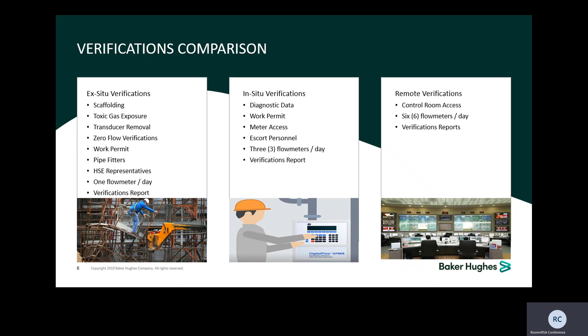We're able to do digital verifications thanks to the Flare.IQ software. It pulls information out, and I have a schematic that talks about this. All this information is sent back to the DCS connected to our Flare.IQ box, and from there we get all the data and analysis to determine pass or no pass. Because our guys go out to the DCS control room, we don't have to access the site directly - we do about 6 meters per day this way, covering more meters per day doing it this way. Again, we have a schematic that goes into more detail.